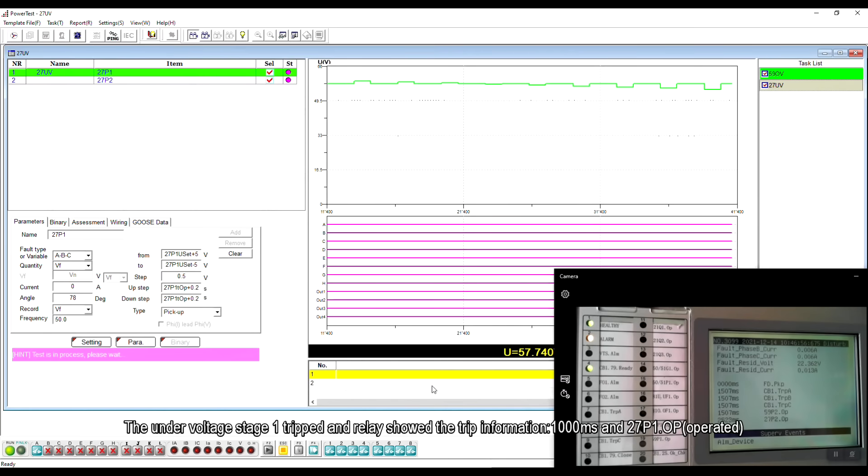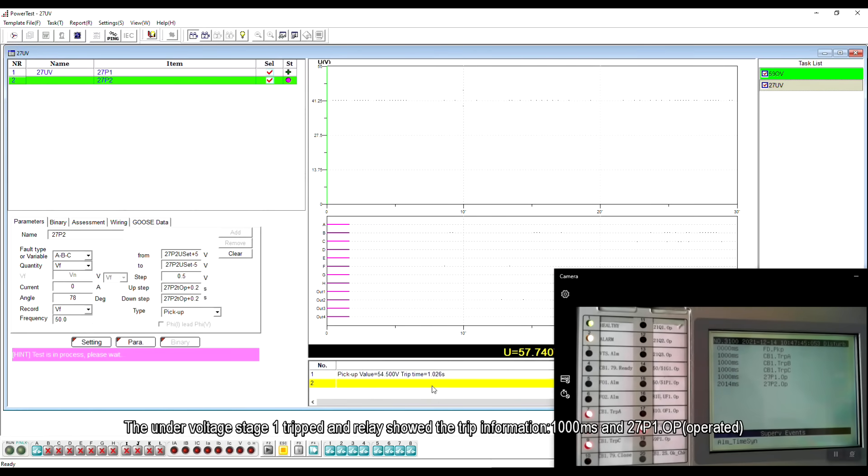The under-voltage stage 1 tripped and the relay showed the trip information, 1,000 milliseconds and 27P1 operated.